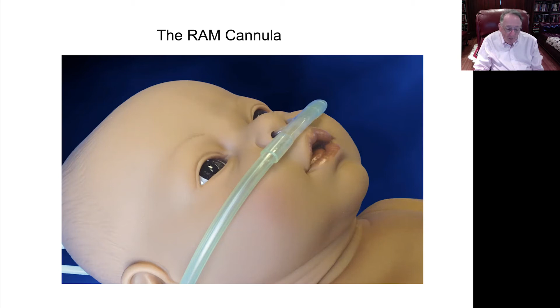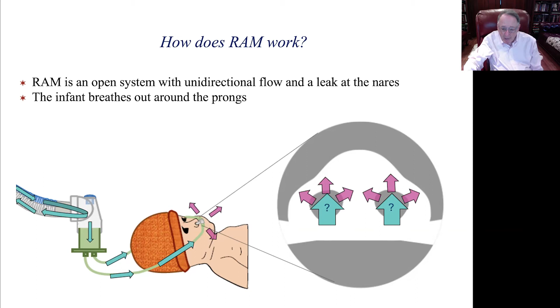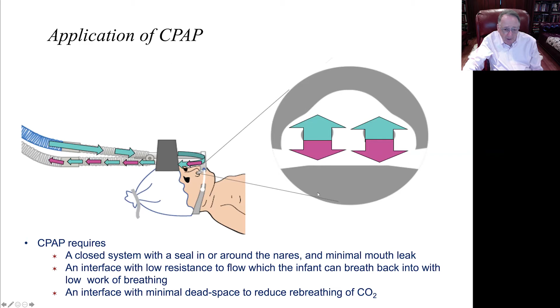The RAM cannula is much different than CPAP. There's no inspiratory and expiratory limb. It's just an inspiratory limb, and the baby breathes out around the prongs. And as you know, when you apply the prongs of the RAM cannula, they're very soft, and nurses like them. They cause fewer abrasions in the nostril, but you need space between the RAM cannula and the baby's nares. Generally, you fill about 60 or 70% of the baby's nares. CPAP is very different. There's an inspiratory and expiratory limb. You try to get a good seal around the nares so the prongs fit fairly tight, and you like to have a low resistance circuit with minimal dead space.